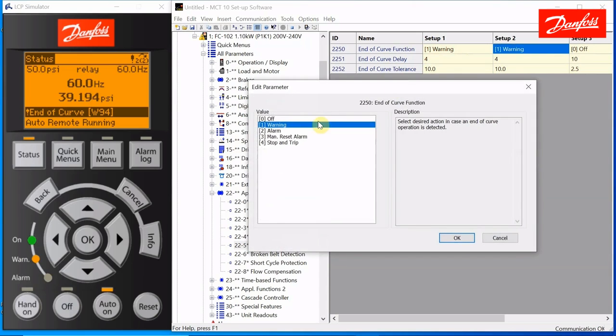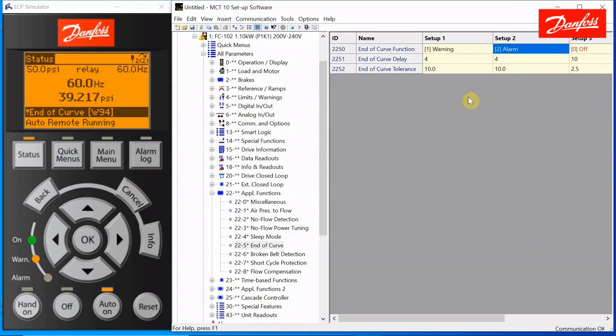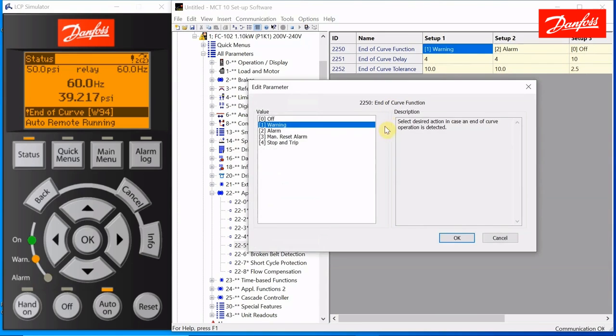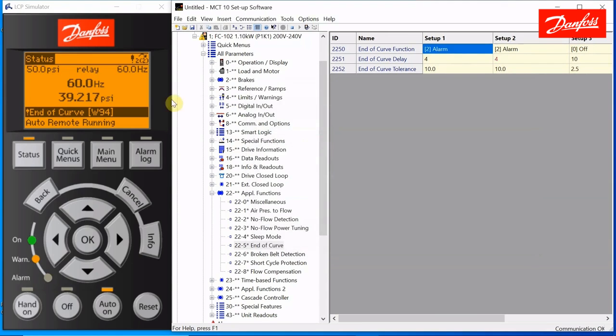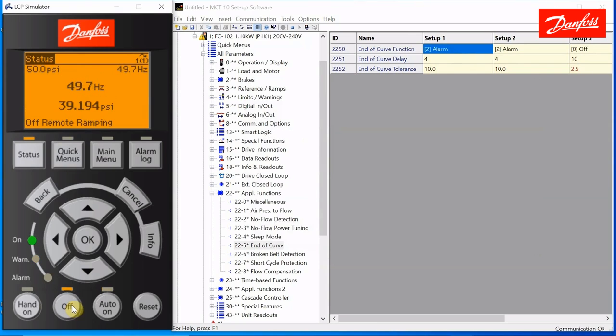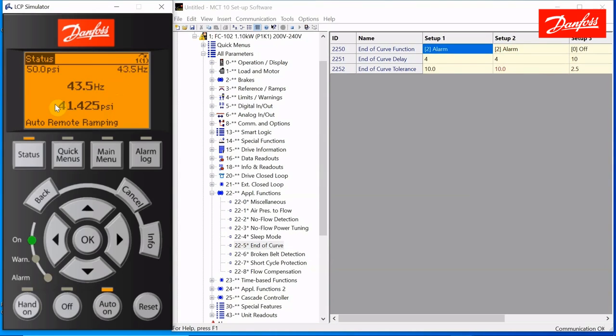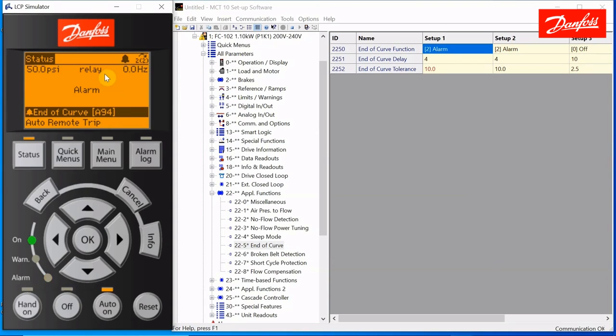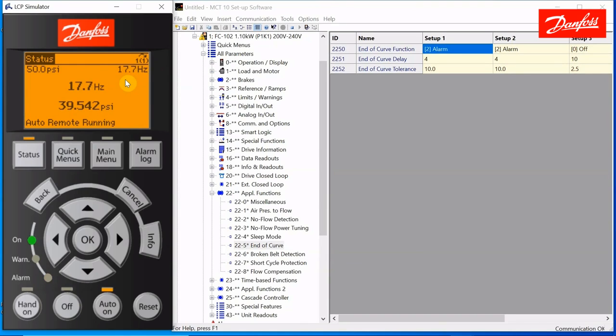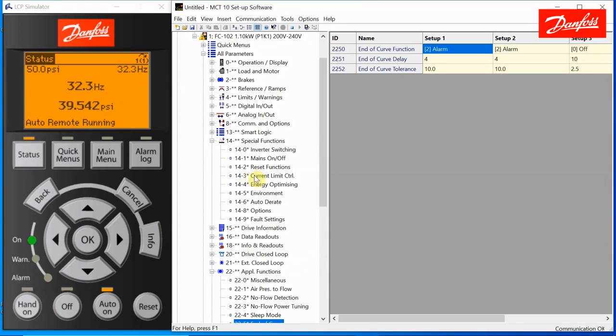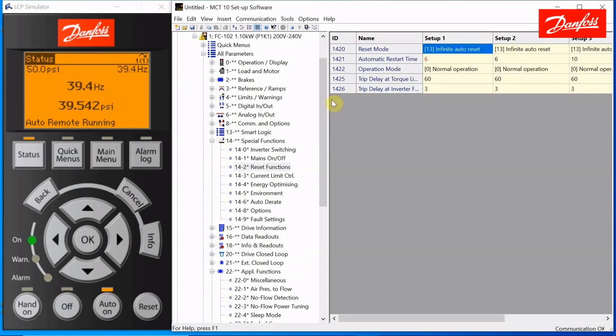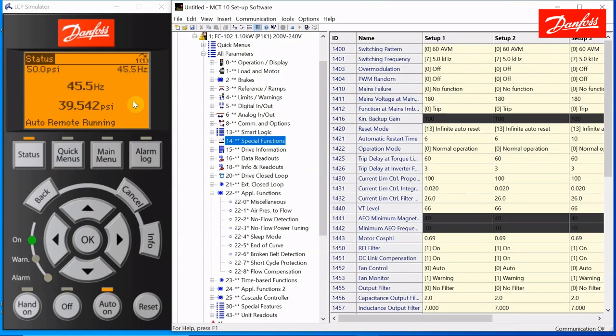Now, rather than warning, let's say we program that for alarm. And let's stop and start again. Ramping back up. Pressure's low. Let's get it above 40. It's going to slowly wind up to 60 hertz. Now this time, when I hit the end of curve trip condition, notice up here what the speed does. You're running along, and suddenly you can't make pressure because you've got a broken pipe. The pressure drops below the threshold. You're at full speed, and four seconds later, it shows the alarm. It triggers the relay, and it immediately dropped to zero speed. Now what happened here? The alarm automatically reset, and it's taking off again because the auto reset function is set to infinite automatic reset. Remember, you don't want to do that. You don't want to keep starting into that broken pipe.